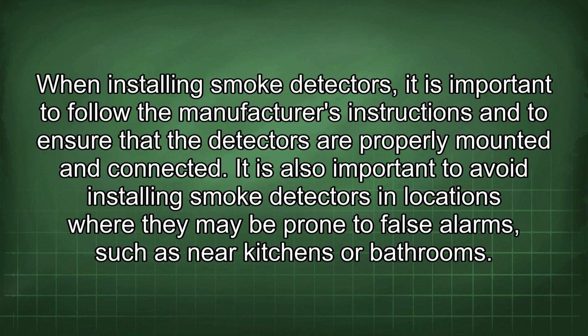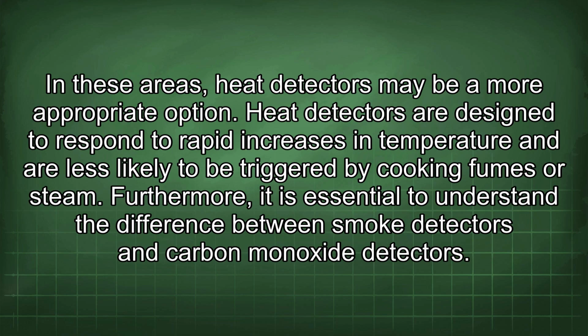When installing smoke detectors, it is important to follow the manufacturer's instructions and to ensure that the detectors are properly mounted and connected. It is also important to avoid installing smoke detectors in locations where they may be prone to false alarms, such as near kitchens or bathrooms. In these areas, heat detectors may be a more appropriate option. Heat detectors are designed to respond to rapid increases in temperature and are less likely to be triggered by cooking fumes or steam. Furthermore, it is essential to understand the difference between smoke detectors and carbon monoxide detectors.